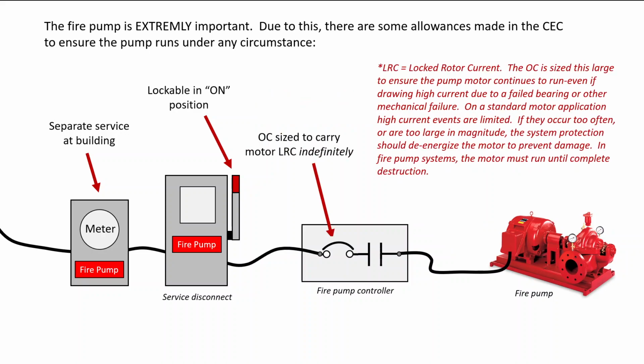The overcurrent for this motor is sized to carry the motor LRC indefinitely. LRC is the locked rotor current. This is the amount of current that would flow if the motor was prevented from turning. It would be humongous. Now the overcurrent is sized this large to ensure the motor pump continues to run even if drawing high current due to a failed bearing or other mechanical failure. On a standard motor application, high current events are limited. If they occur too often or are too large in magnitude, the system protection should de-energize the motor to prevent damage. In fire pump systems, the motor must run until complete destruction.